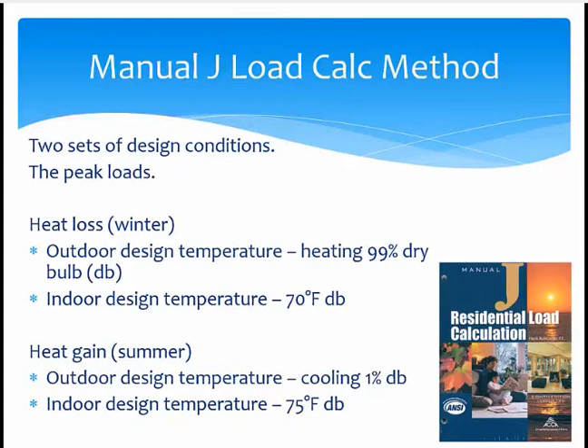For the summer, we also have two design temperatures used for the load calculation. The outdoor design temperature will be the cooling 1% dry bulb temperature — that is, for only 1% of the year, so slightly more than 80 hours, will it be warmer than this temperature. So it's actually pretty hot, depending on the home's location. Meanwhile, the indoor design temperature in the summer is going to be 75 degrees Fahrenheit dry bulb.